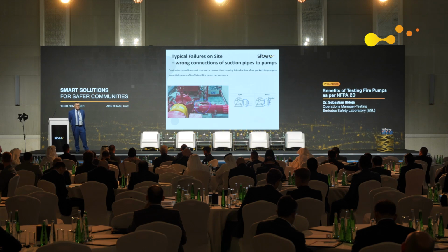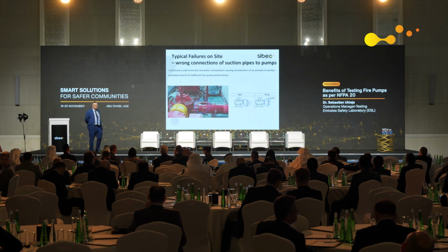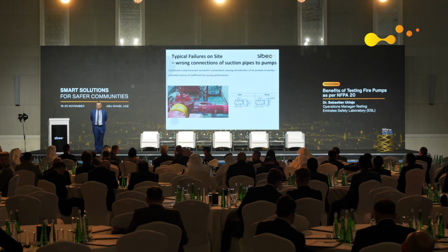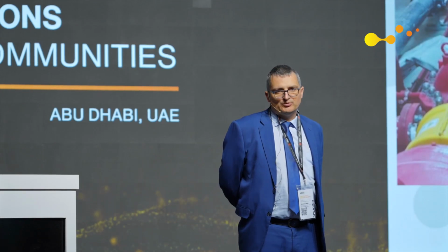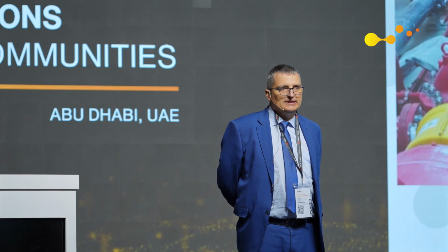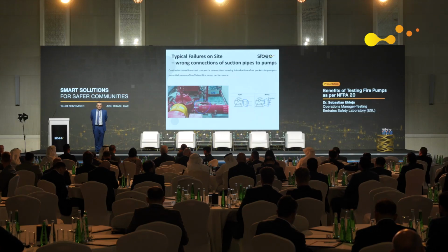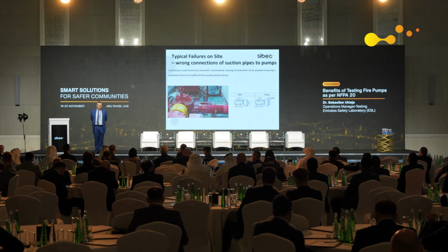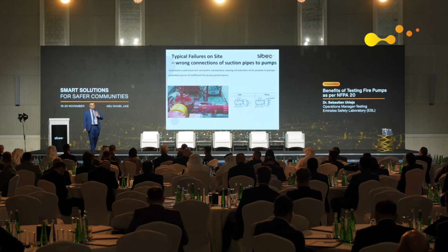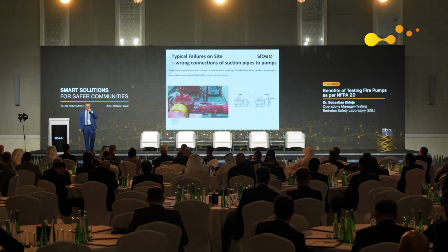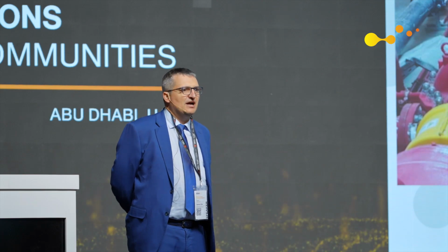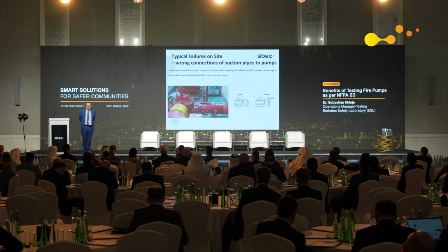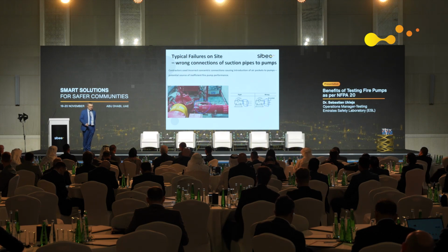There is a really comprehensive procedure described in NFPA 20 in chapter 14, which clearly mentions what should be tested, how it should be tested, and why it should be tested. And only then can we ensure that a given system will be operational during a fire, or we have high confidence that it will be operational during fires. As I said, I'm not touching any maintenance. I'm not checking any regular annual or three-year testing. We're talking only initial commissioning. So my message is the pumps are very good, but we have to improve the way they are installed here or in any other country where fire pumps are being used.